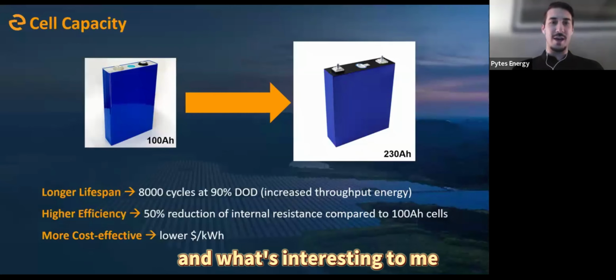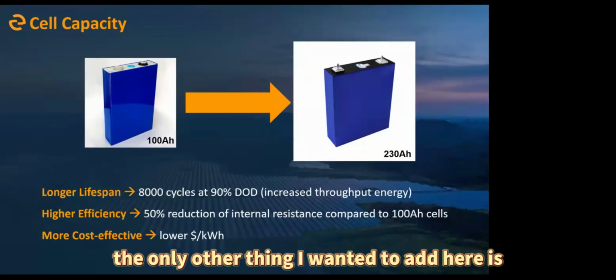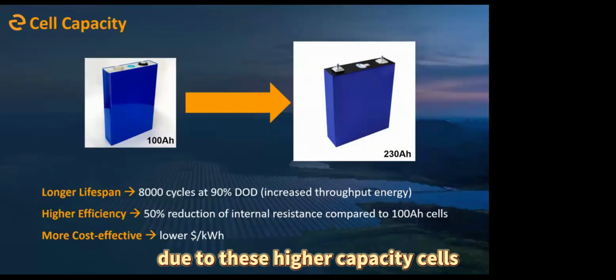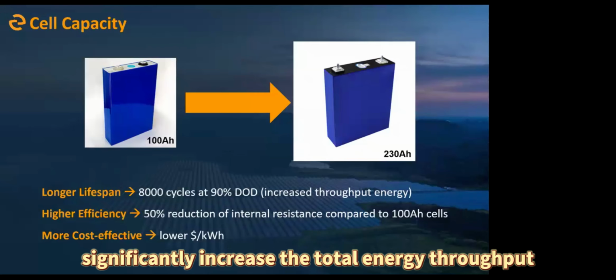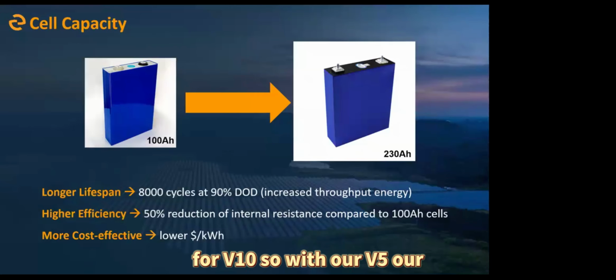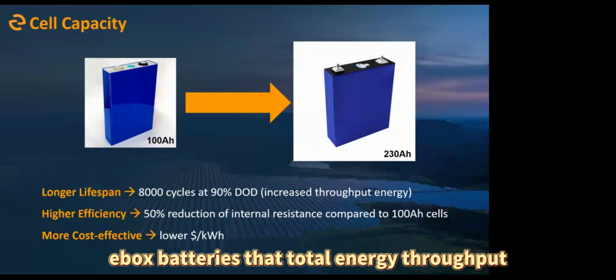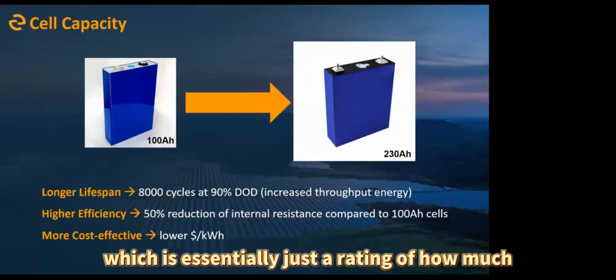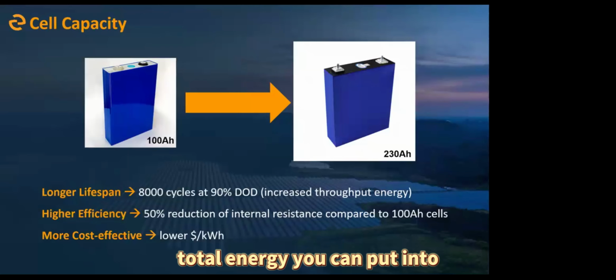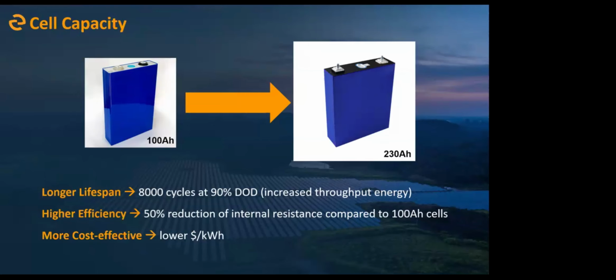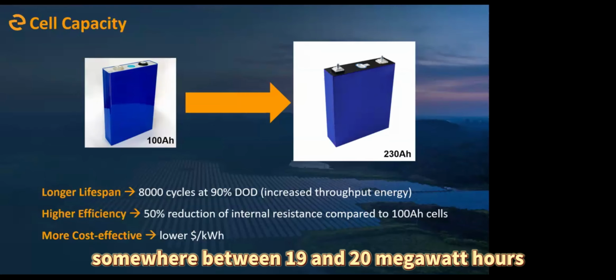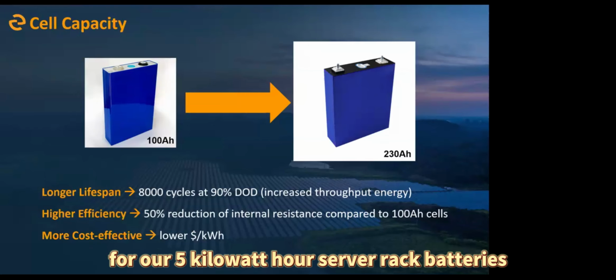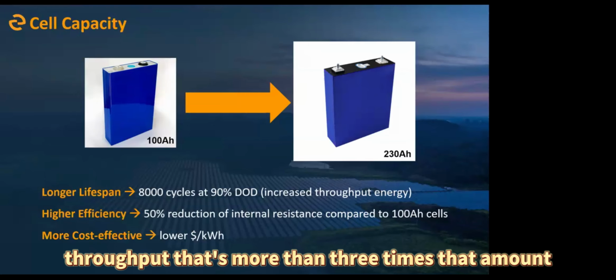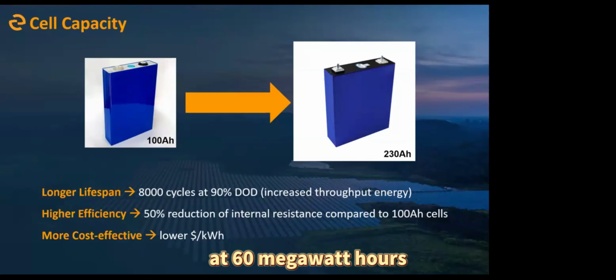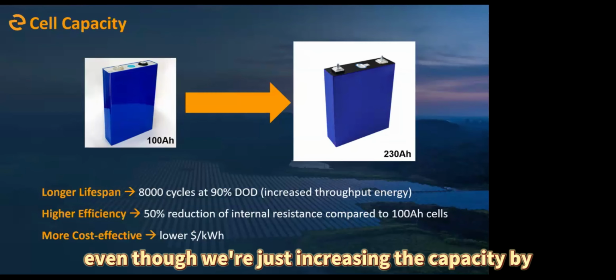What's interesting to me is because we have these higher capacity cells, we've actually been able to significantly increase the total energy throughput for V10. With our V5 and eBox batteries, that total energy throughput - essentially a rating of how much total energy you can put into or take out of the battery throughout its entire life - is about 19 to 20 megawatt hours for our 5 kilowatt hour server rack batteries. V10 is going to have a throughput more than 3 times that amount, at 60 megawatt hours, even though we're just doubling the capacity.